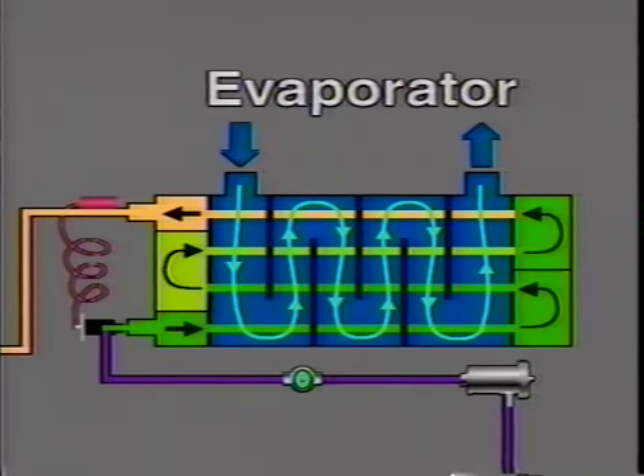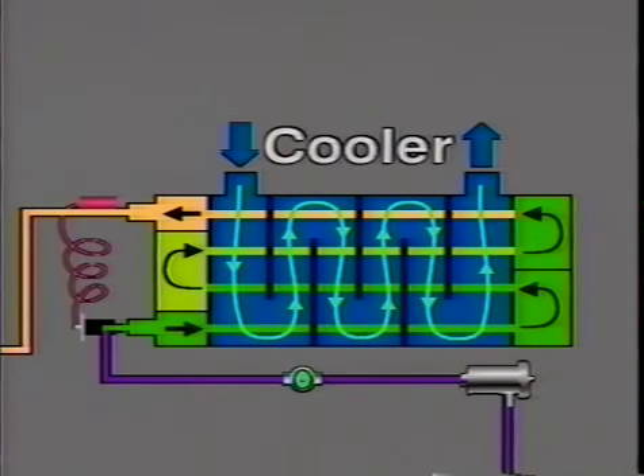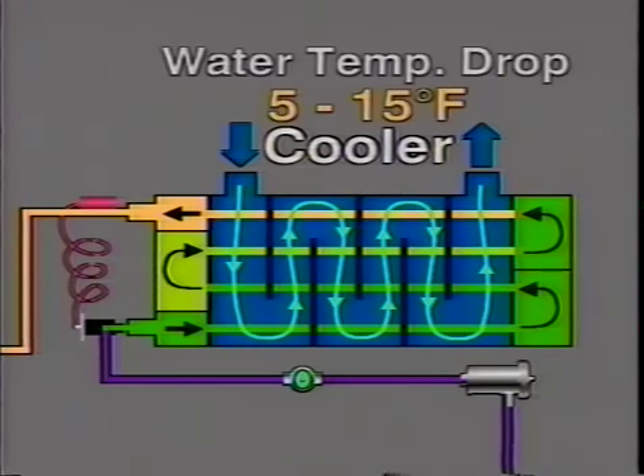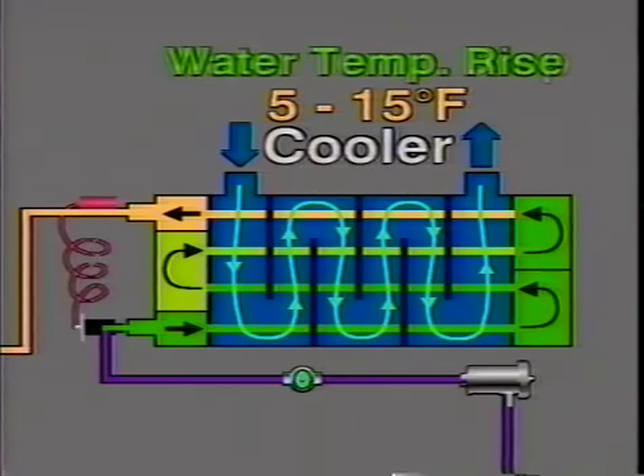In a typical direct expansion type water chiller, the evaporator is called the cooler, where refrigerant flows inside the tubes and water flows outside the tubes. The water gives up heat to the refrigerant, and under full load conditions, the water temperature drop through the cooler will be, depending on design, between 5 and 15 degrees Fahrenheit, with 10 degrees Fahrenheit being typical. This is also stated as the water temperature rise. It occurs in the water loop external to the cooler.